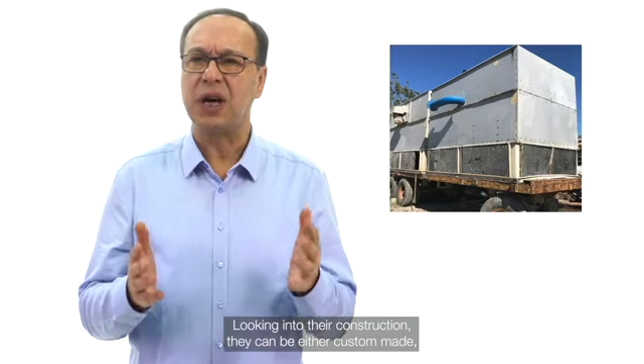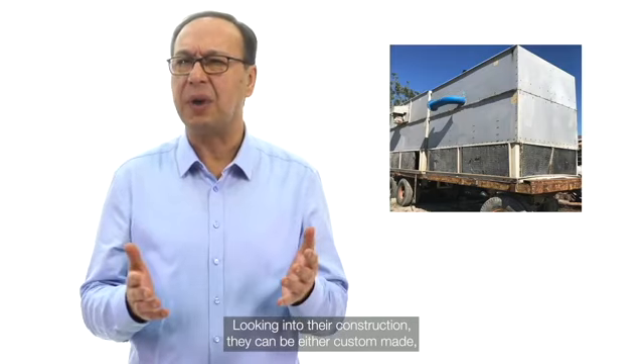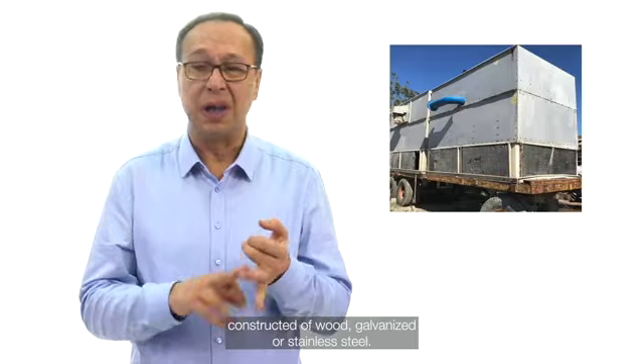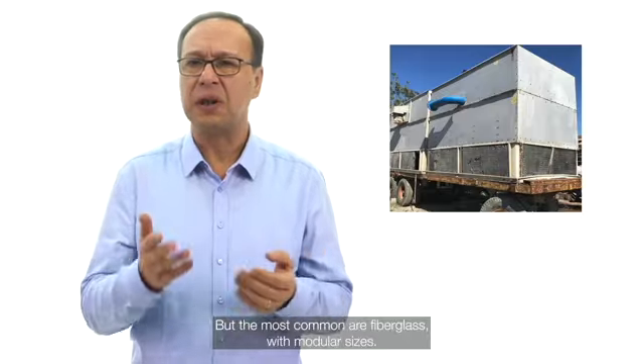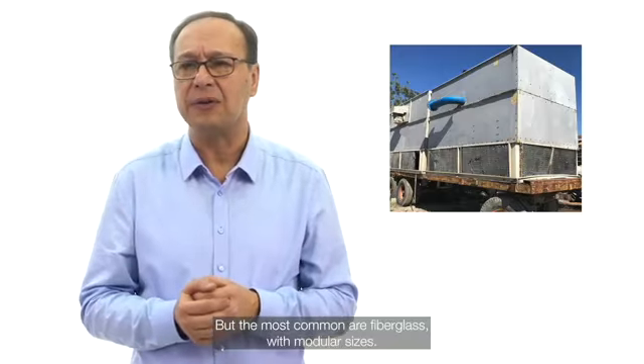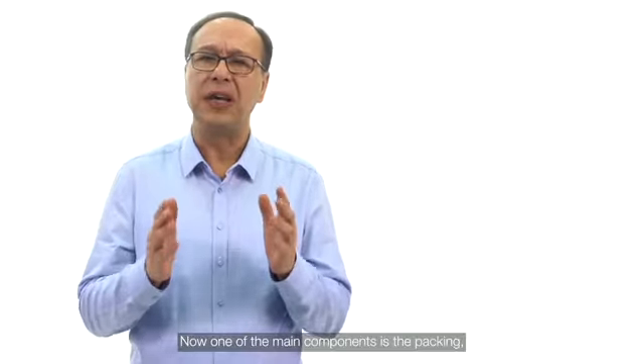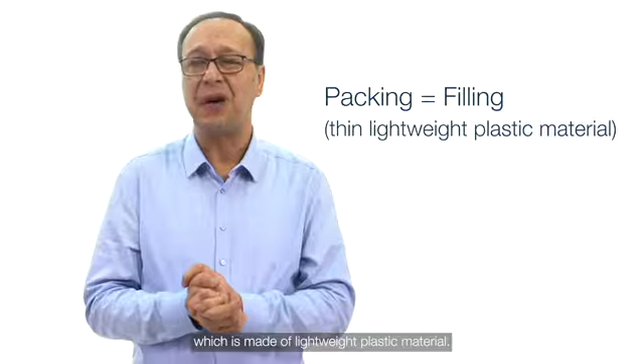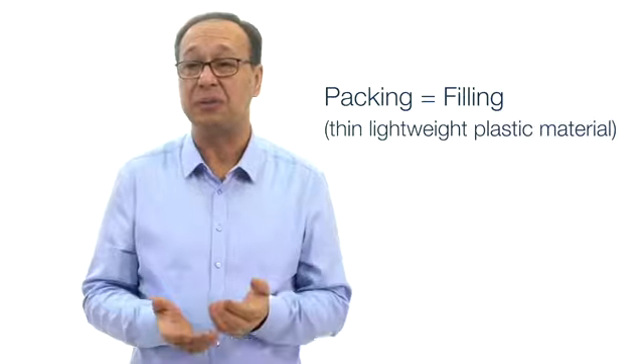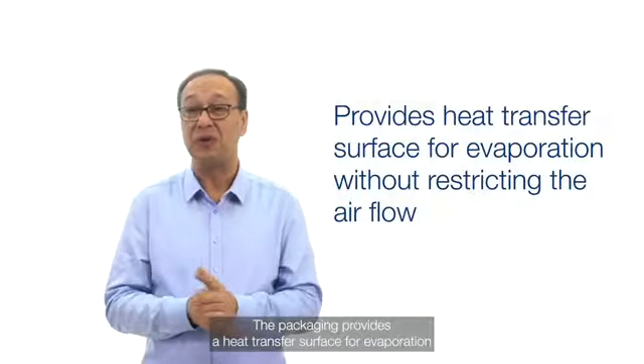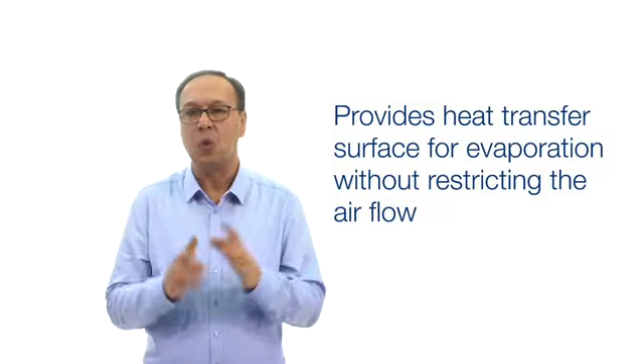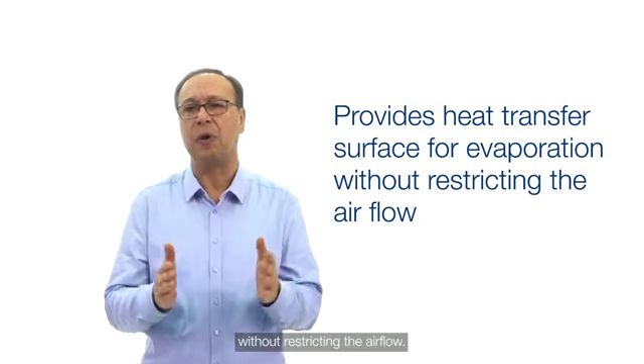Looking into their construction, they can be either custom made, constructed of wood, galvanized or stainless steel, but the most common are fiberglass with modular sizes. Now, one of the main components is the packing, which is made of lightweight plastic material. The packing provides a heat transfer surface for evaporation without restricting the air flow.